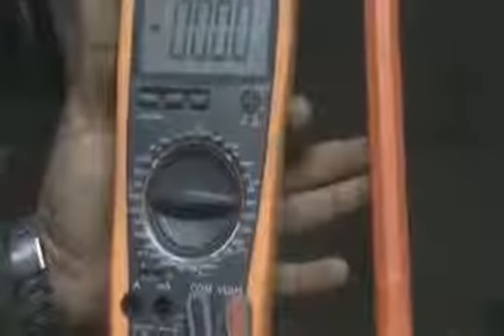First of all we will see the instrument in no load condition, in which we will measure the high voltage produced by the high voltage transformer with the help of a high voltage probe and a digital multimeter. The probe has an attenuation ratio of 1000:1, so if we apply 10,000 volts to the top of the probe we will get 10 volts at the measuring point, which is easily measurable by any digital multimeter.